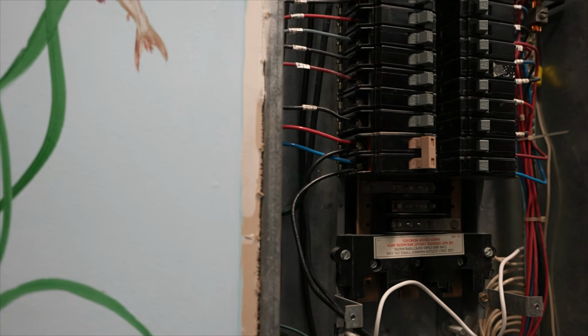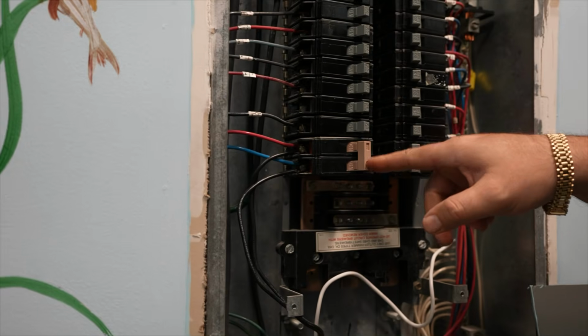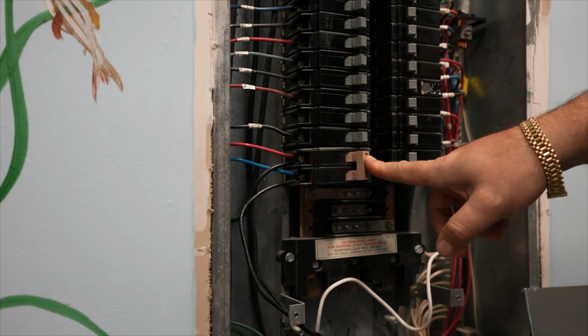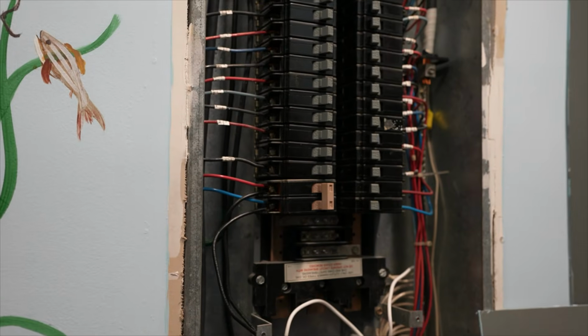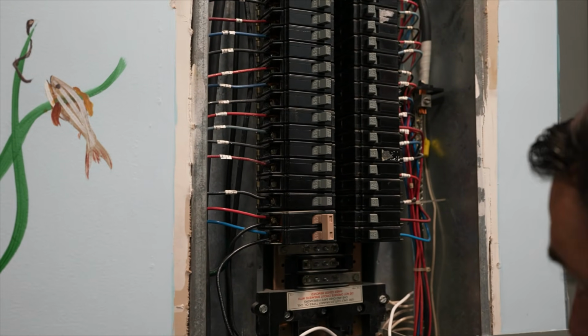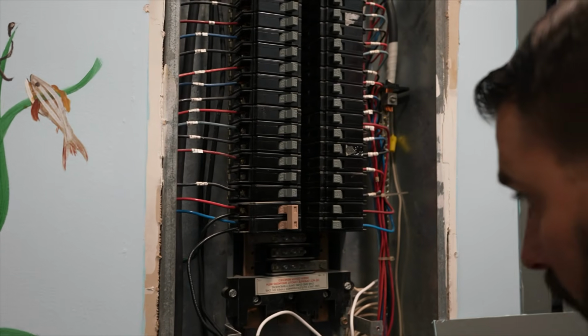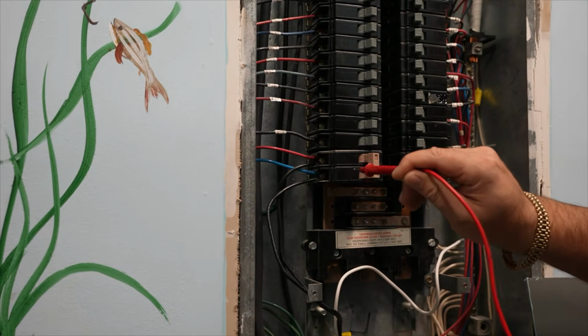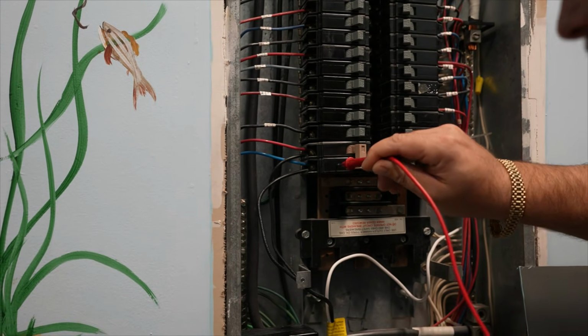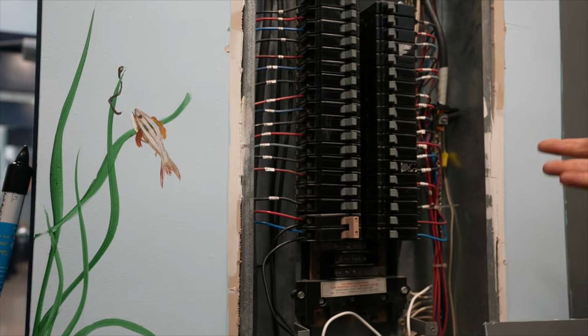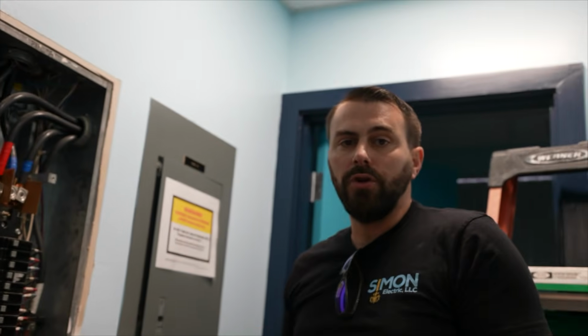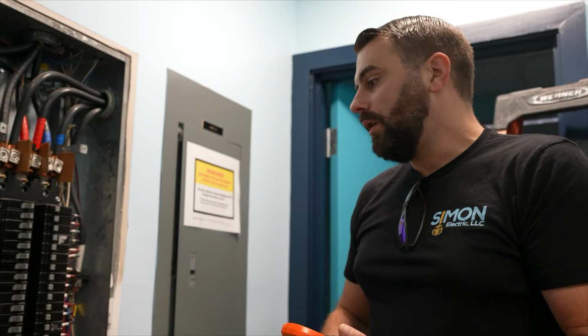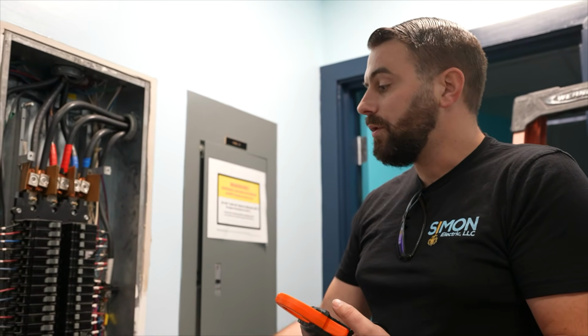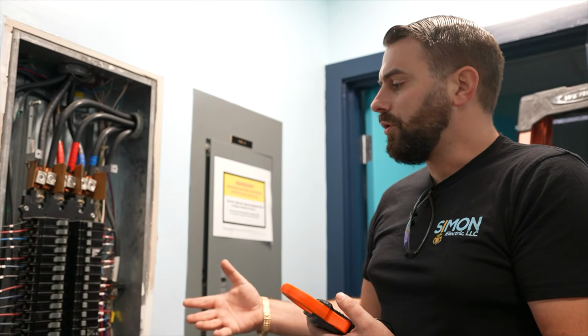The other aspect of this is three-phase. This surge protector is only actually providing surge protection to, I'm not sure what legs, B and C legs, because the next one down is A leg. So this is A, B, and C, and this surge protector is only getting B and C - it's not a three-leg surge protector. I don't know if they took that into consideration and made sure the components they're trying to protect are on the B and C leg. But the fact that it's double tapped and also only a single-phase surge protector doesn't give me a lot of confidence that the electrician took that into consideration.